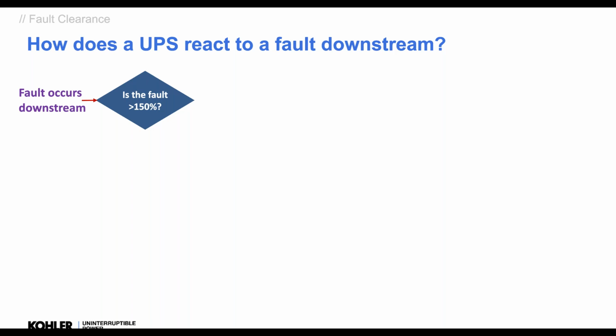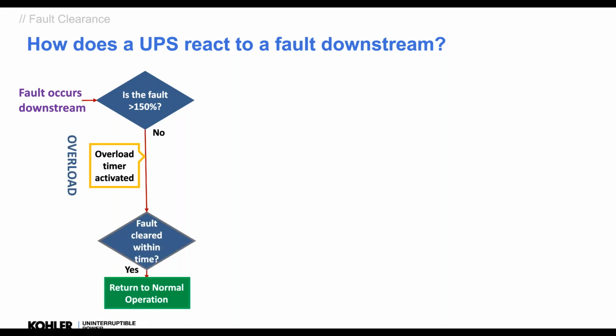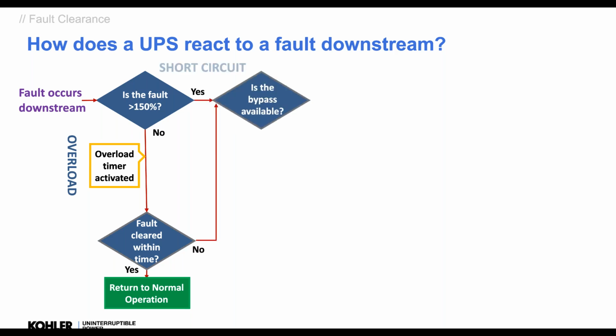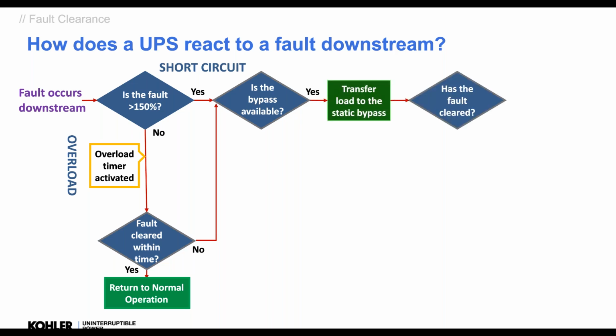So if the fault is under 150%, we can treat it as an overload. We start the timer. It's an exponential timer, but most UPSs can do 150% for 30 seconds to a minute. And we try and use that to clear the fault. And if it does, it's great. We go back to normal, say it's had an overload. But if not, we treat it as a short circuit. And the first thing the UPS will ask is, is the bypass available? Have I got mains? Is it available? Because if it is, it will transfer the load to the bypass in about 3 or 4 milliseconds, extremely quickly. And we use the mains now to try and clear the fault.